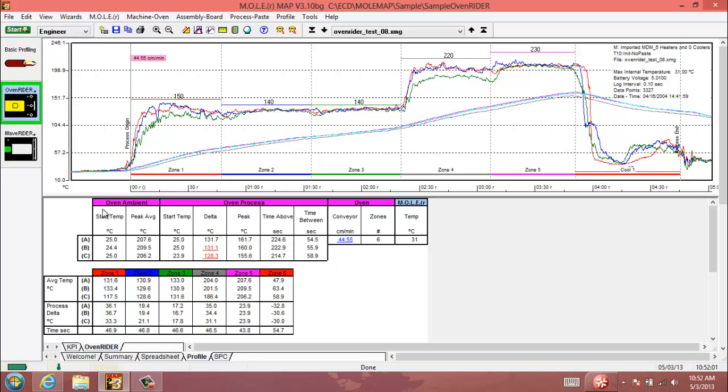Starting off here, the Oven Ambient - these are figures for each sensor, A through C, just beginning at your process origin temperature, basically when you first put it into the oven or the very beginning of Zone 1.